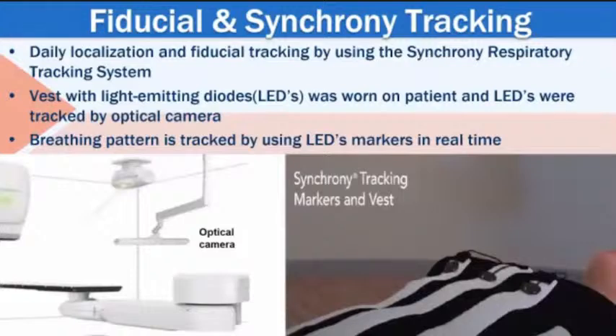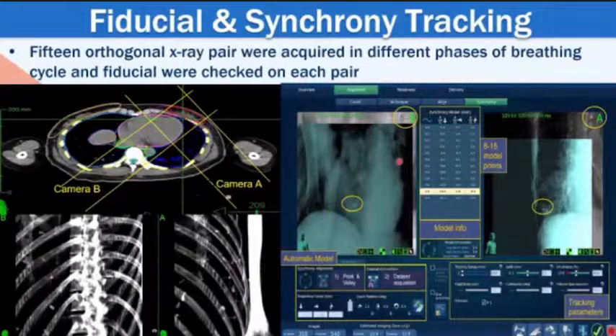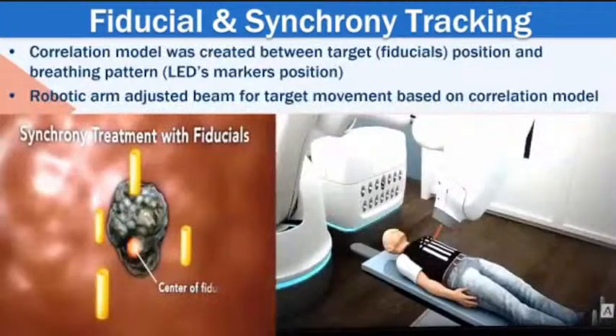A light-emitting diode vest was worn by the patient, and the LEDs on the top were tracked by an optical camera. The breathing pattern of the patient was then tracked in real time according to the chest wall position. 15 orthogonal X-ray pair images were acquired in different phases of the breathing cycle, and fiducial positions were tracked on each imaging pair. As a result, a predictive correlation model was created between target position and breathing pattern according to fiducials and LED markers position. The target beam was then adjusted by the robotic arm for target movement based on this correlation model, as shown in this movie.